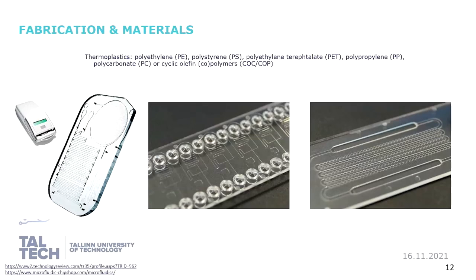Now let's talk about plastics. When we talk about plastics I mean thermoplastics — plastics that are injection molded, hot embossed, or thermoformed in another way. This is an example of a polymer chip that has a reactor or incubation chamber, a waste pad or collector pad, various mixing channels with solid reagents, and sample input ports. Another example is a demo slide with a bunch of different ports to which you can connect tubing, with channels inside — this is actually a droplet generator chip with various sizes of junctions. The good thing is the slide itself is really cheap to make, transparent, high quality, and the reproducibility is good.